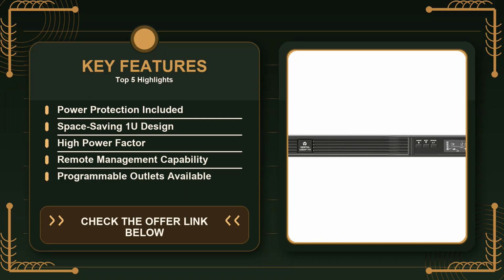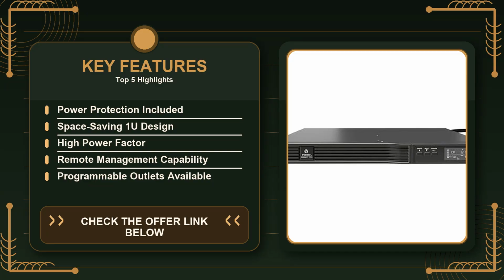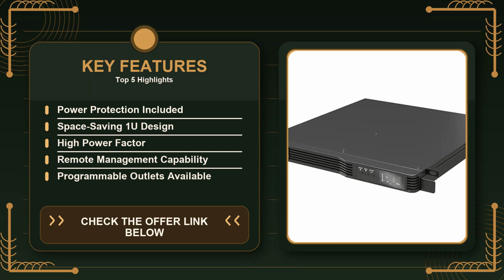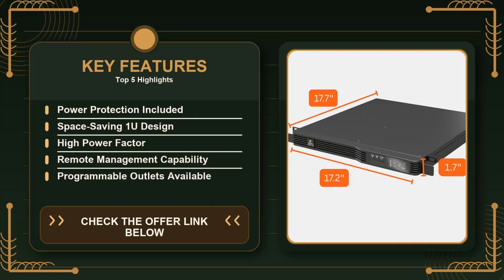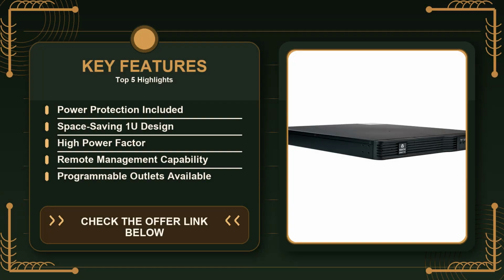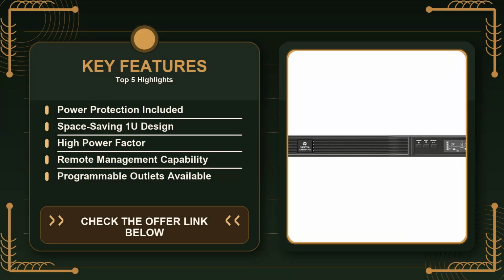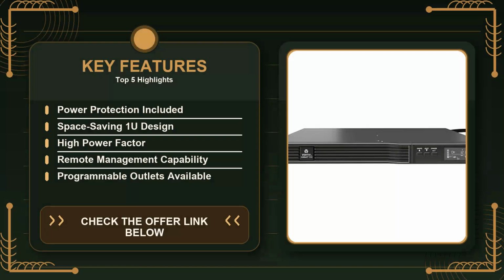On the flip side, if you're only looking to back up a single home PC or a router, you'll likely be overpaying. The 1U rack form factor is great for data centers but unnecessary for a bedroom setup. Likewise, enterprises that need megawatt-scale backup or long-run hours should look at larger, modular UPS solutions rather than this mid-range unit. One practical strength that shows up in real-world deployments is the space-saving design. In a 42U rack, every unit counts, and being able to tuck a UPS into a single slot frees up room for additional servers or storage.